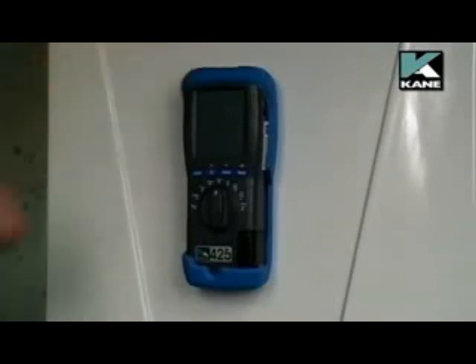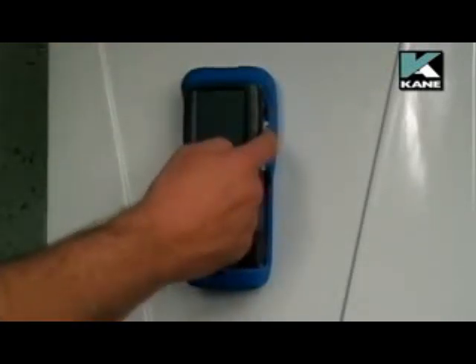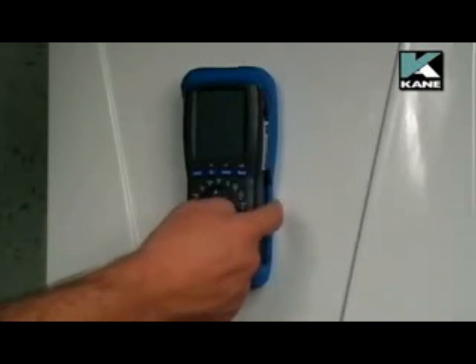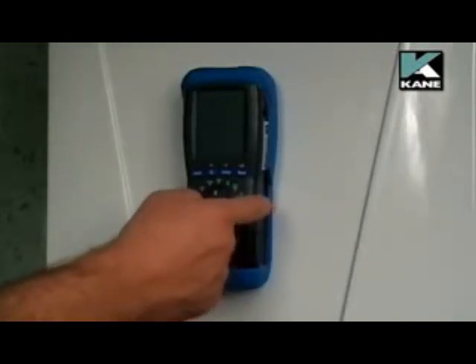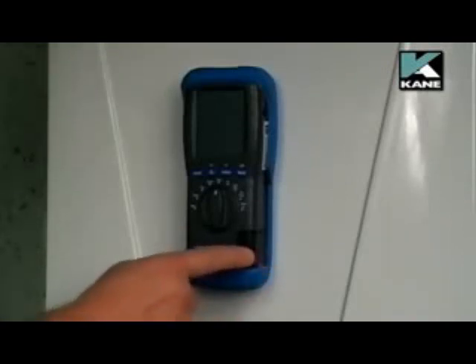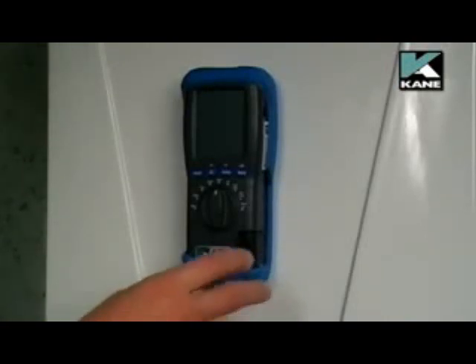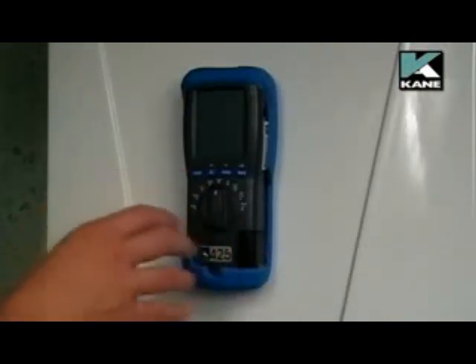On the top of the analyzer you have an infrared emitter which will send the information to the printer. There's also an inbuilt torch. On this side of the analyzer you have a socket for a gas leak detector, which is just a plug-in unit. Coming a bit further down, again on the side of the analyzer you'll be able to see a white filter, which is the particle filter. Here we have the water trap, which will take out any condensate to make sure that the sample of gas going to the analyzer is a clean, dry sample.